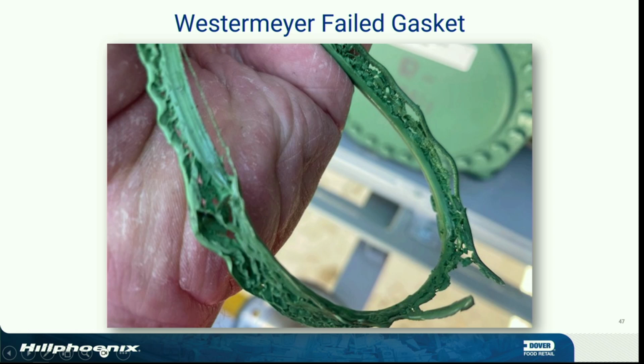So before you do an oil change, your separator change, have you check your filter, open it up, look at your gasket. Make sure you don't have one of these rubber gaskets. Did you see that? I put it on, took it off. It looked like that. It crushed it, just trying to stop it from sealing.